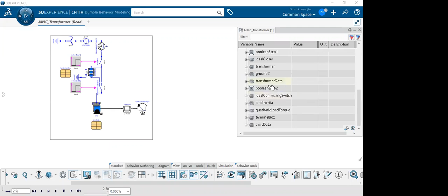Next, you can check all the parameters. If you want to check the transformer data, like V1, V2, you can see one phase voltage is 57.735 volt and one phase current is 288.675 ampere. Now, I was telling you that whenever load increases, current demand increases. See, voltage is just 58 volt, but current is 288.675 ampere. Can you imagine 288.675 ampere? In our households, we use only 5 to 6 ampere. Now see the demand.